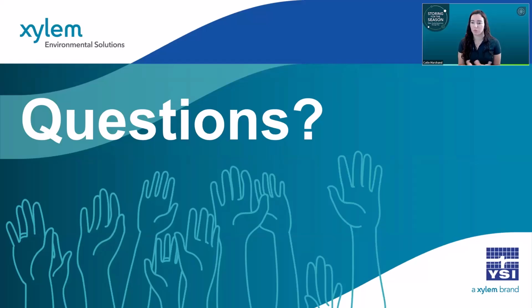Especially if you have a deployment, you have your sensors out in the field and they stay out in the field, we recommend starting with going back to check on them at least once per month, if not every couple weeks, to make sure that everything's working well. You're not getting buildup on your sensors while they're deployed, they're getting good data, and you're not experiencing drift.